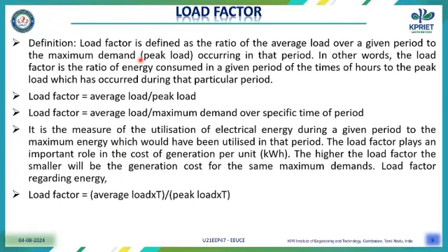Next, we are going to see the load factor. What is load factor? Load factor is defined as the ratio of the average load over a given period to the maximum demand, or we can say the peak load occurring in the period. In other words, the load factor is the ratio of energy consumed in a given period of hours to the peak load which has occurred during that particular period.